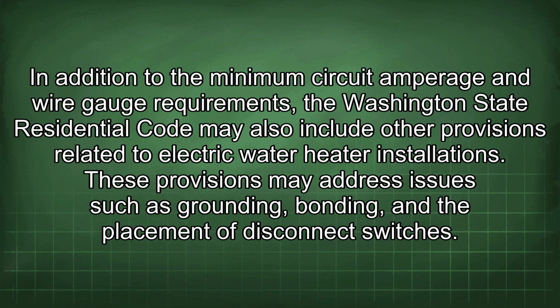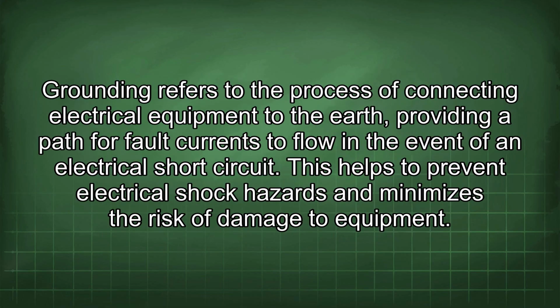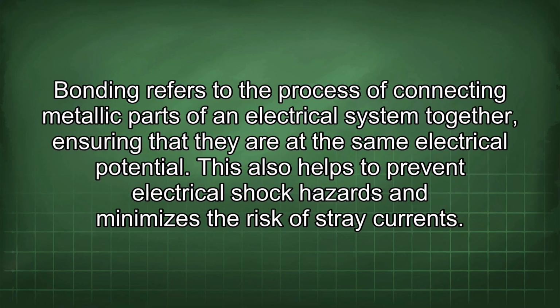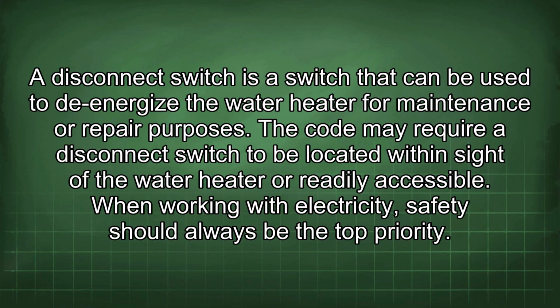In addition to the minimum circuit amperage and wire gauge requirements, the Washington State Residential Code may also include other provisions related to electric water heater installations. These provisions may address issues such as grounding, bonding, and the placement of disconnect switches. Grounding refers to the process of connecting electrical equipment to the earth, providing a path for fault currents to flow in the event of an electrical short circuit. This helps to prevent electrical shock hazards and minimizes the risk of damage to equipment. Bonding refers to the process of connecting metallic parts of an electrical system together, ensuring that they are at the same electrical potential. This also helps to prevent electrical shock hazards and minimizes the risk of stray currents. A disconnect switch is a switch that can be used to de-energize the water heater for maintenance or repair purposes. The code may require a disconnect switch to be located within sight of the water heater or readily accessible.